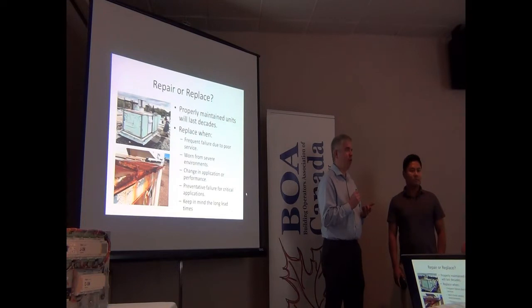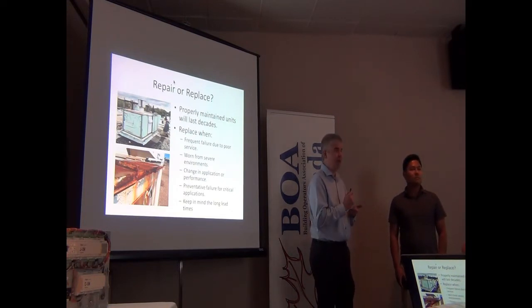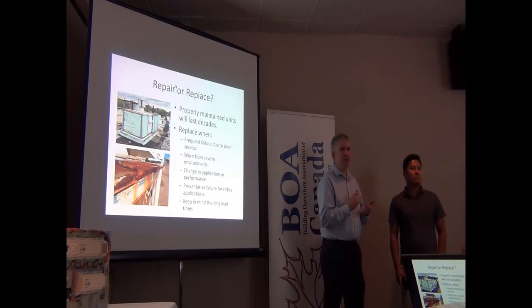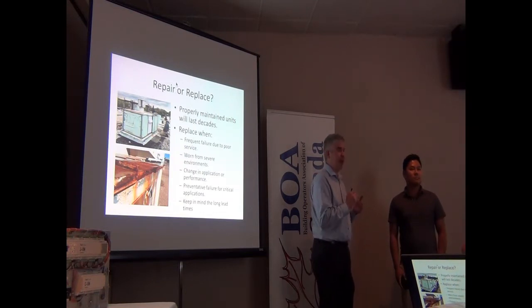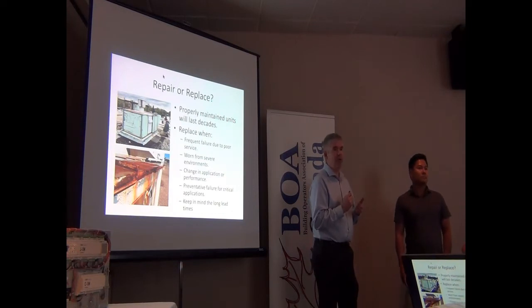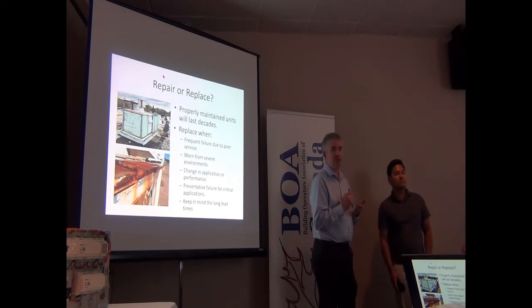Would that be something to talk with or ask an engineer about? We can find out, look at the unit, see how it was designed, how close it is, and determine whether a little bit of change in static is actually going to radically affect your fan performance curve in the first place. So how does that affect the curve from 8 to 13?